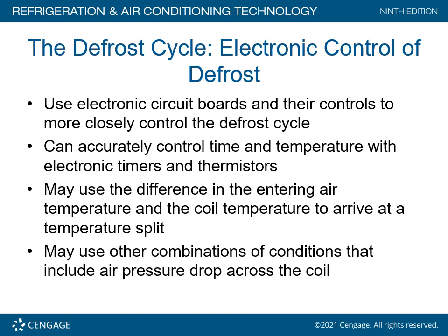Electronic control defrost utilizes electronic circuit boards. That's typically what you're going to find on equipment today. These controls more closely control the defrost cycle. They can accurately control time and temperature with electronic timers and thermistors. Personally, I like the boards a lot better than the old mechanical timers that I got involved with back in the late 70s and early 80s. They may use the difference in the entering air temperature and the coil temperature to arrive at a temperature split. They may utilize other combinations or conditions that include air pressure drop across the coil.